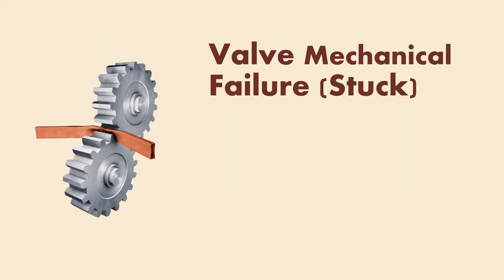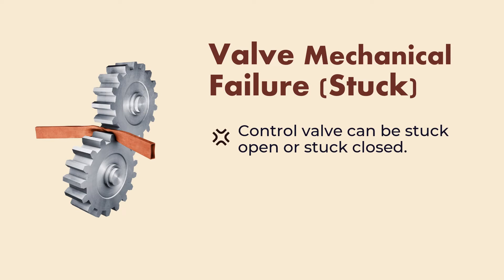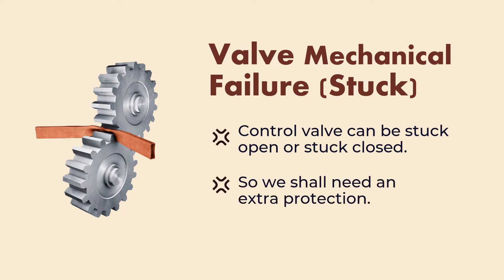Although air failure is the most common reason for control valve malfunctioning, there is also a probability of mechanical failure. For example, if the valve stem was stuck open or closed, then this would mean that the air supply wouldn't help, and we won't get the valve at its fail safe position. So sometimes we will even need external protection for the upstream or downstream equipment to prevent any potential damage due to valve failure.